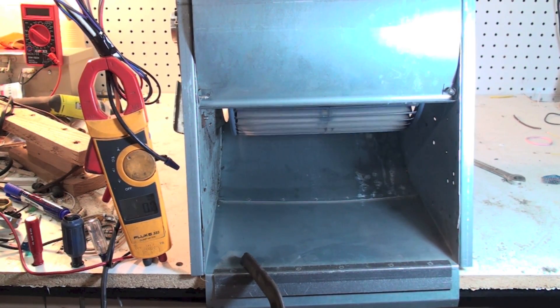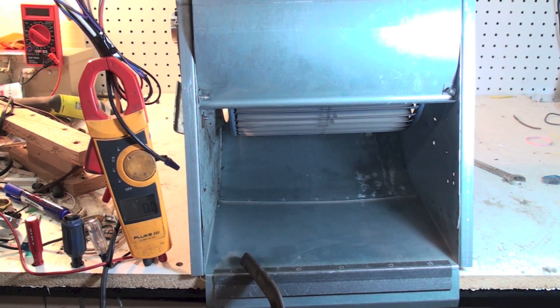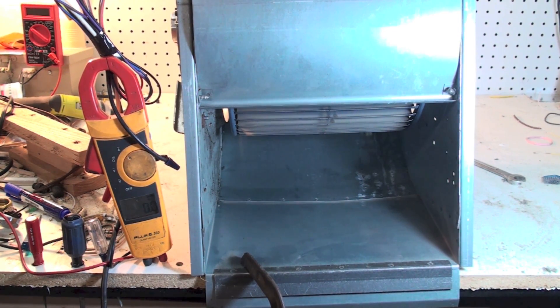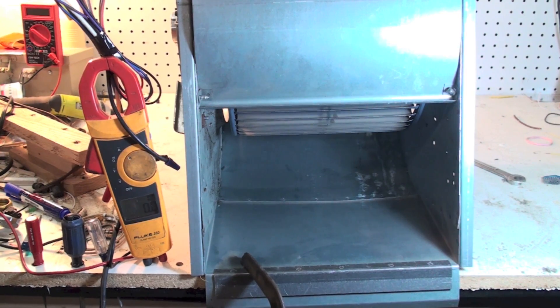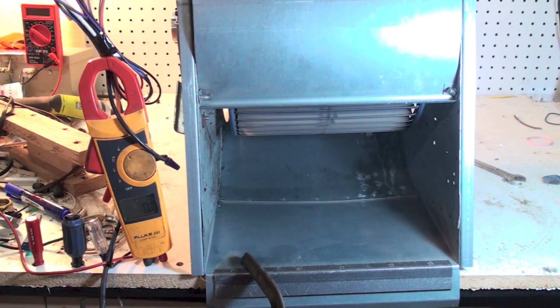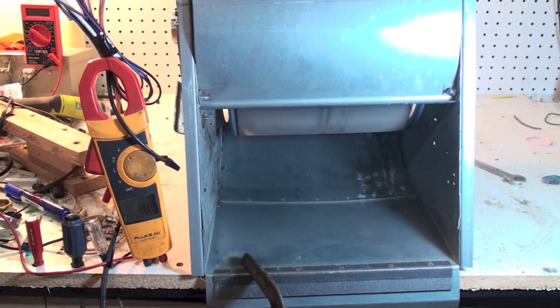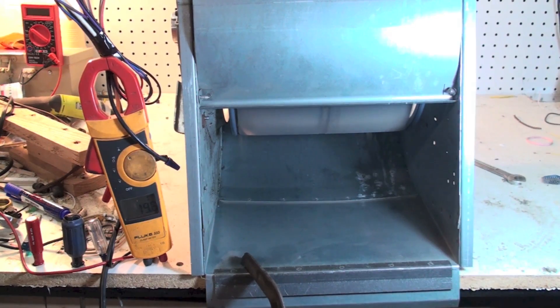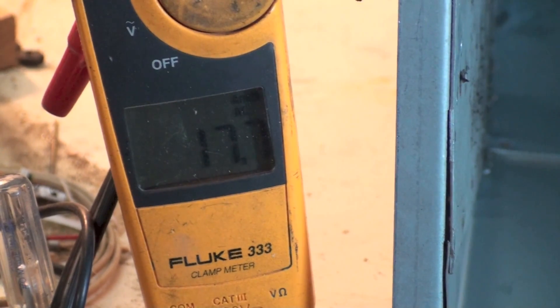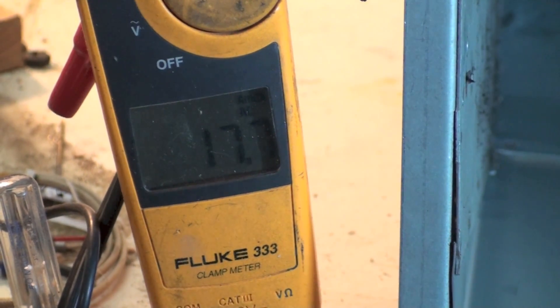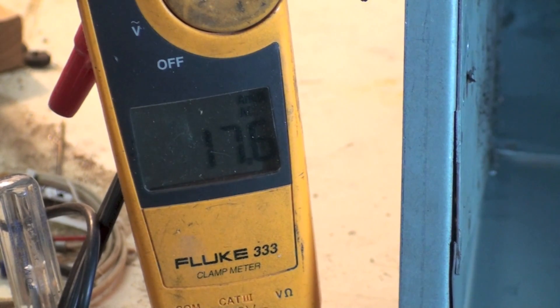For those of you that have seen some of my earlier videos, this is the same blower I had before that I demonstrated blower loads and amp draw. And so this thing is going to do the same thing as it did in the other video. You can see the amp draw is 17.8 and the normal amp draw for this blower is 9.1.